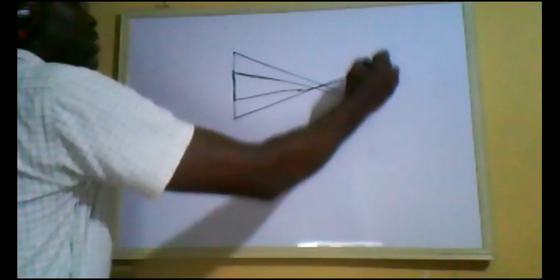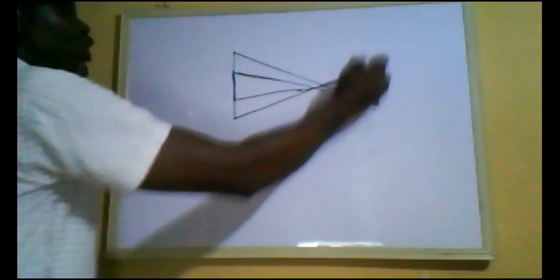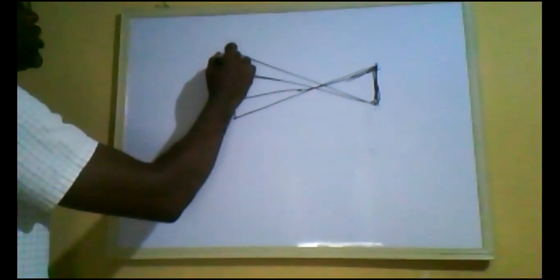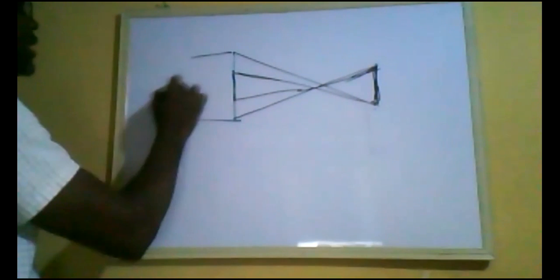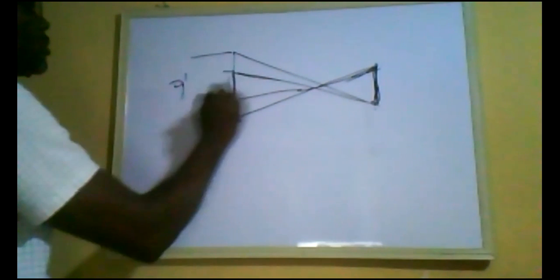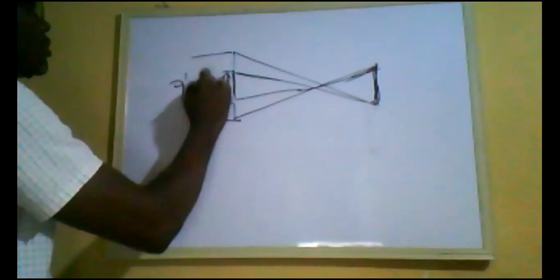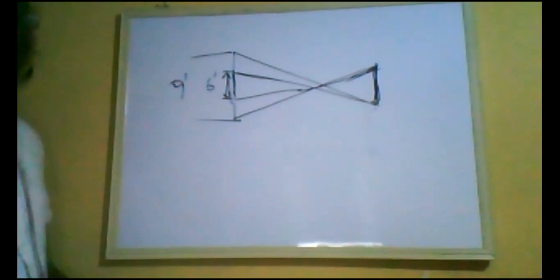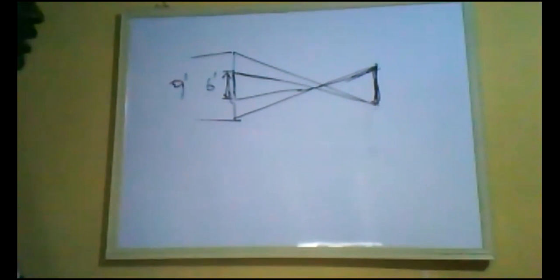Of course, the image will always be formed using the total length of the output phosphor. So this one can be our 9-inch, while this one is 6-inch. With this, we have activated the magnification mode of the image intensifier.